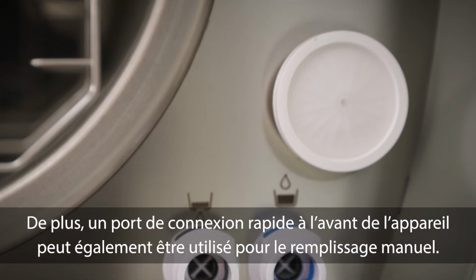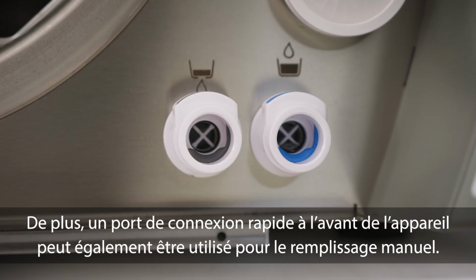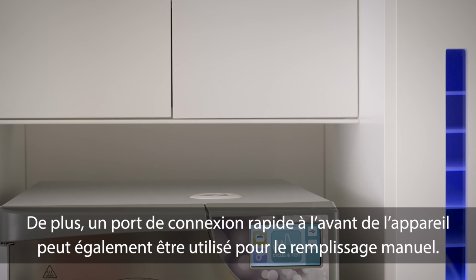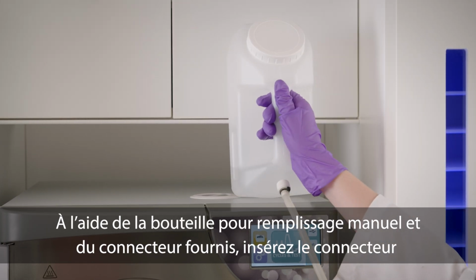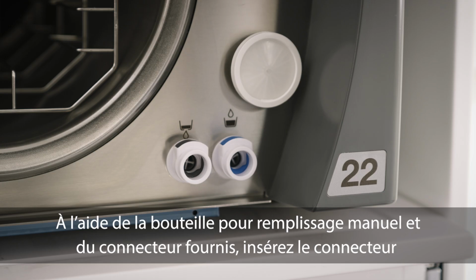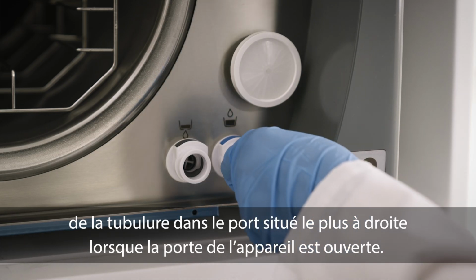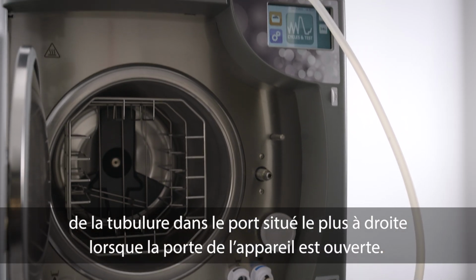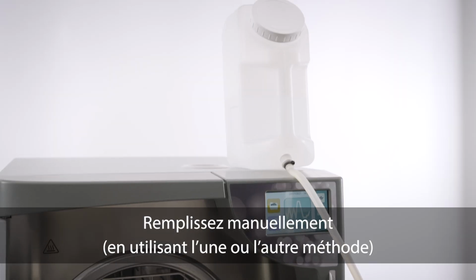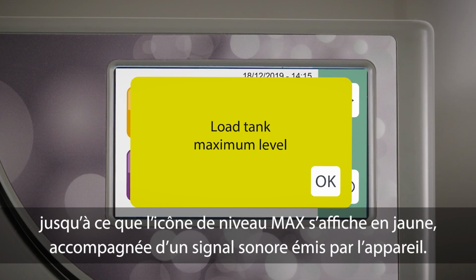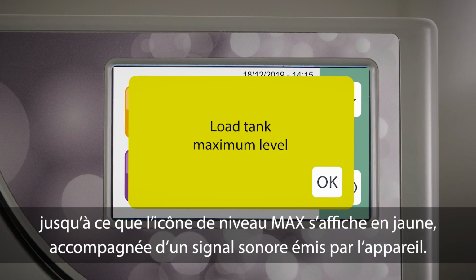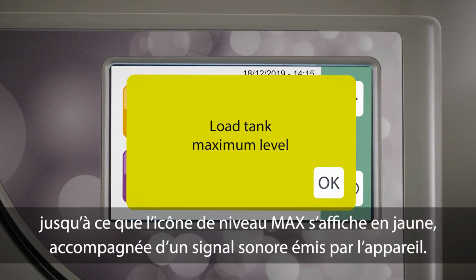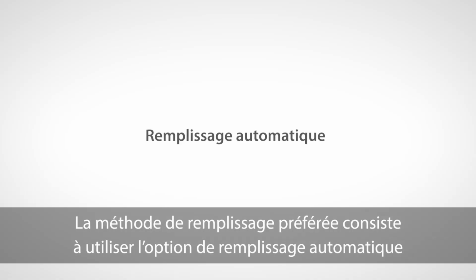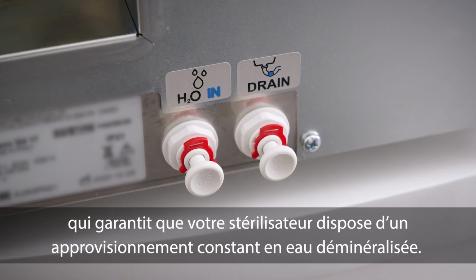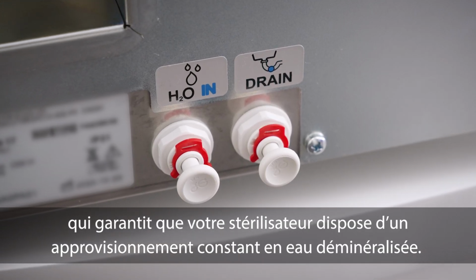As well, there is a quick connector port at the front of the unit that can also be used for manually filling. Using the manual fill bottle and connector provided, insert the tubing connector into the port located to the farthest right when the unit door is open. Manually fill, using either method, until the max level icon appears on the screen in yellow, accompanied by a beeping sound from the unit. The preferred method for filling is to use the automatic filling option, which ensures your sterilizer has a constant supply of demineralized water.